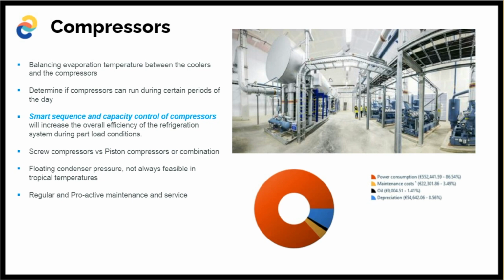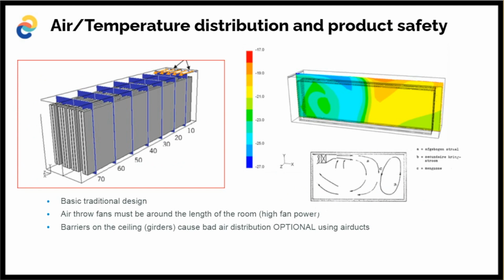So, a few words on air distribution and product safety. As I mentioned, traditionally we have these coolers hanging on top of the cold store and blowing over the product. It could work, but now they're getting bigger and longer. Let's say the maximum airflow of a cooler is around 60 to 70 meters, depending on the cooler supplier. But when you go to 150 meters, you get this kind of effect. As you can see at the bottom right, you see these secondary flows going on in your cold store.